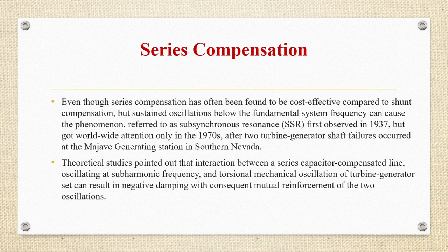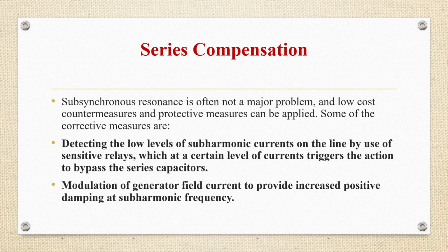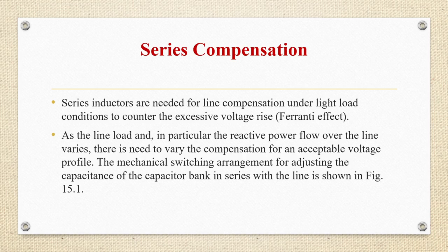So some of the corrective measures are detecting the low levels of subharmonic currents on the line by use of sensitive relays, which at a certain level of currents triggers the action to bypass the series capacitors. Second one is modulation of generator field current to provide increased positive damping at subharmonic frequency. Series inductors are needed for line compensation under light load conditions to counter the excessive voltage rise, that is Ferranti effect. So as the line load and in particular the reactive power flow over the line varies, there is need to vary the compensation for an acceptable voltage profile. The mechanical switching arrangement for adjusting the capacitance of the capacitor bank in series with the line is shown in the figure.